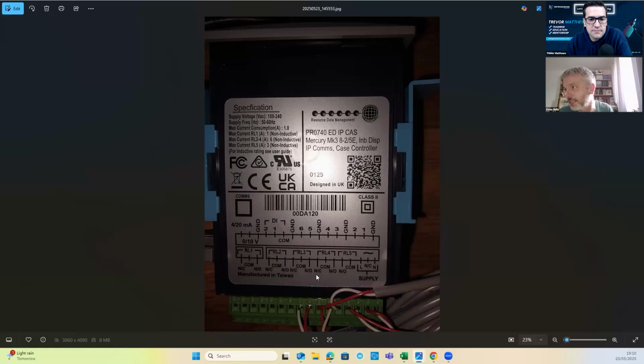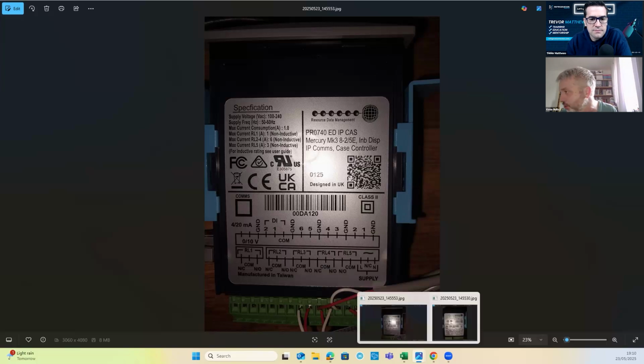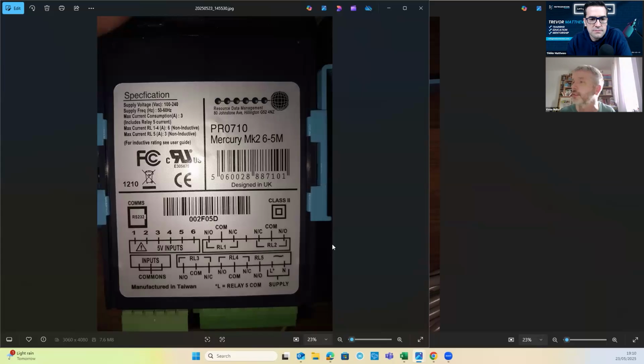On the relays, it's exactly as you would expect. Normally closed, normally open and common. Okay, they're all volt-free relays down there, so you've got to put a supply onto them. If I show you an old one, if I can find, yeah. So this is my old been in the garage 10 years controller, RS232. Okay, so even though the socket looks the same, it's RS232. On the newer ones, it will say it in the model number as well.